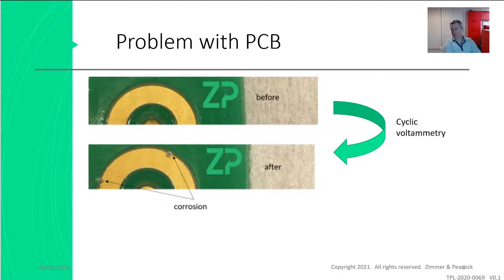When you then visually inspect it, you get these little pits or holes. That's more a problem when you're doing amperometry and voltammetry, because in those applications you're applying voltage, and voltage is energy, and energy or power can help accelerate this corrosion, so a small pinhole could become a much bigger hole.